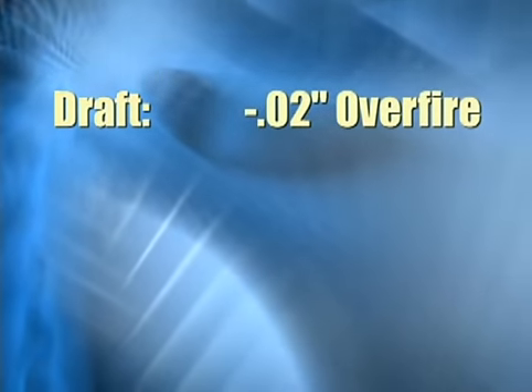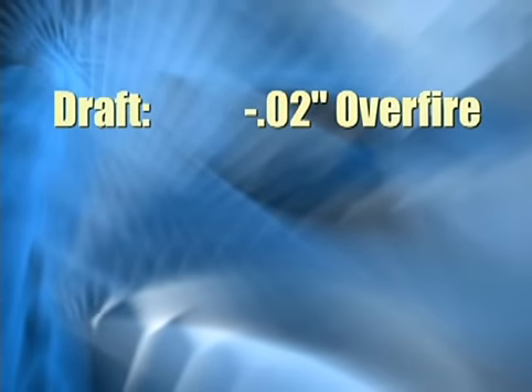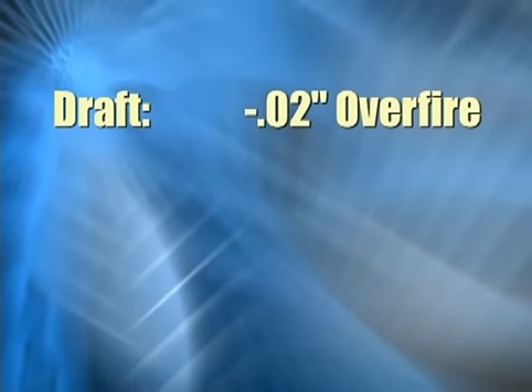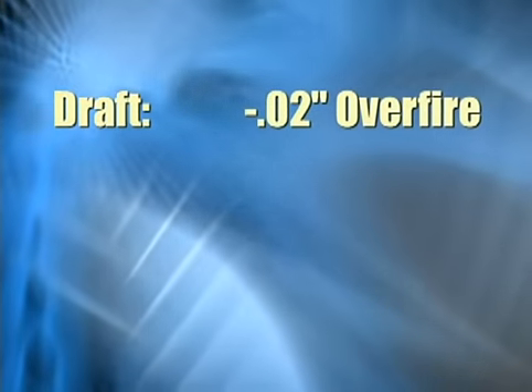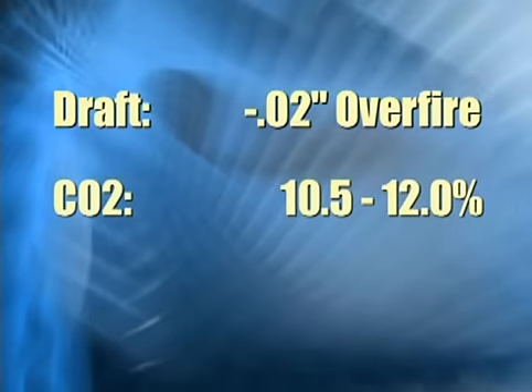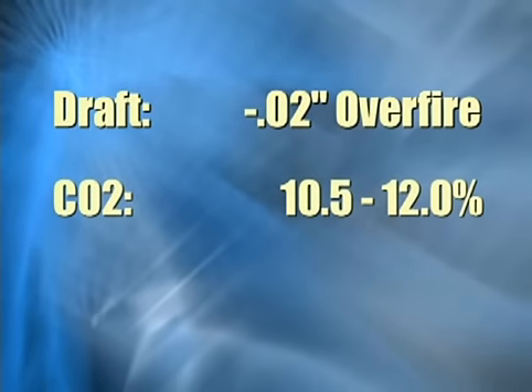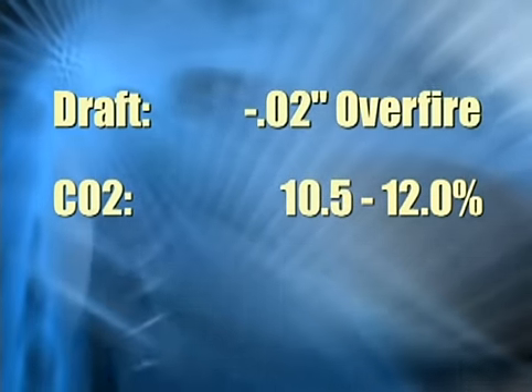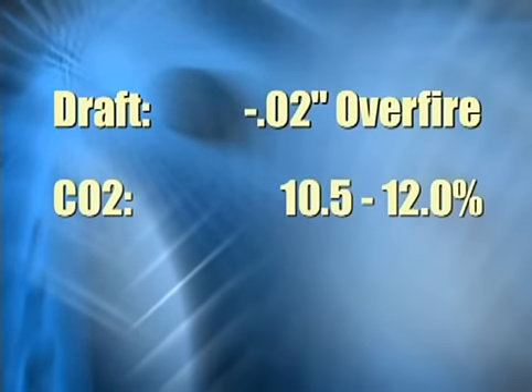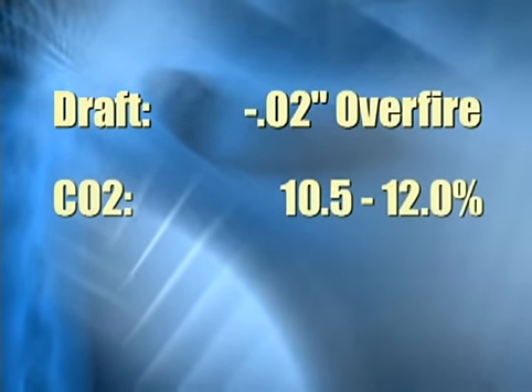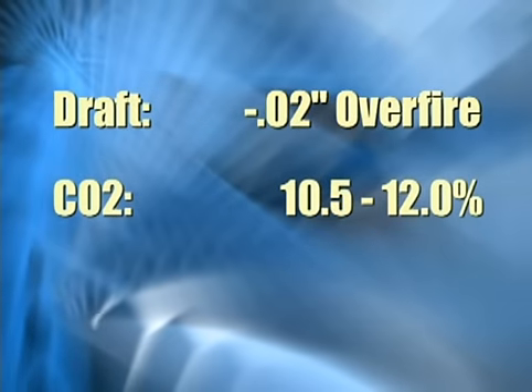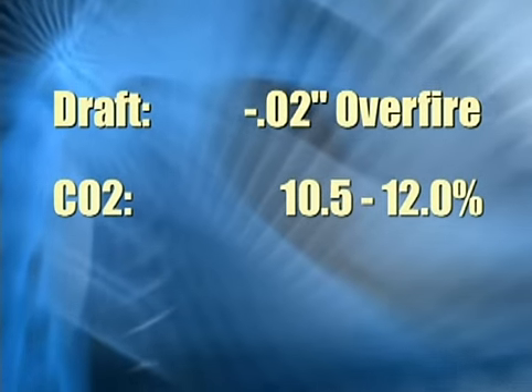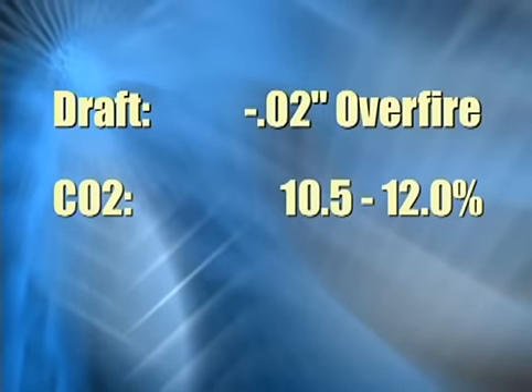Unless the unit is designed for positive pressure, draft over fire should be approximately negative 0.02 inches. Higher draft would lower the efficiency. Lower draft could indicate an improperly adjusted draft regulator, chimney trouble, or an overfired unit. The CO2 reading indicates the amount of excess air introduced into the combustion process. A CO2 reading of 10.5 to 12% would normally be acceptable. Readings below 9% or above 13% indicate the potential of generating smoke and soot.